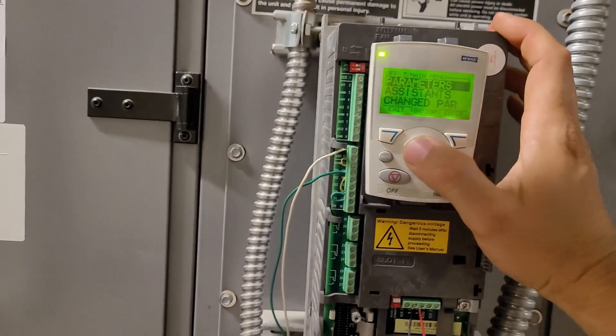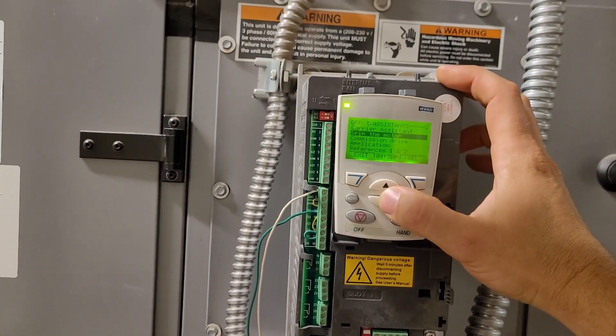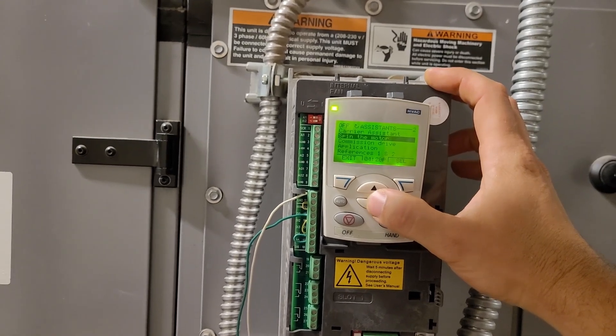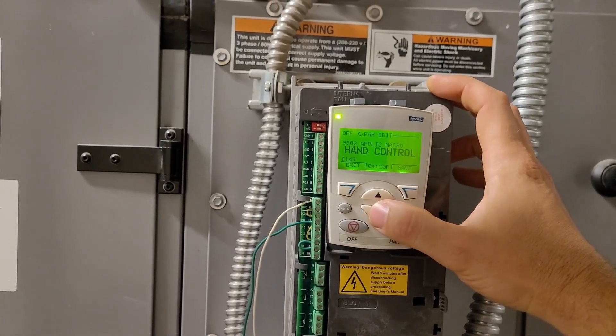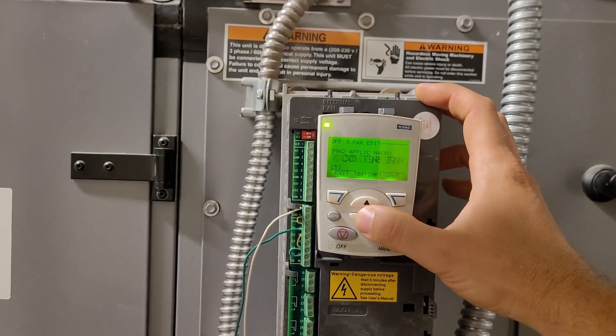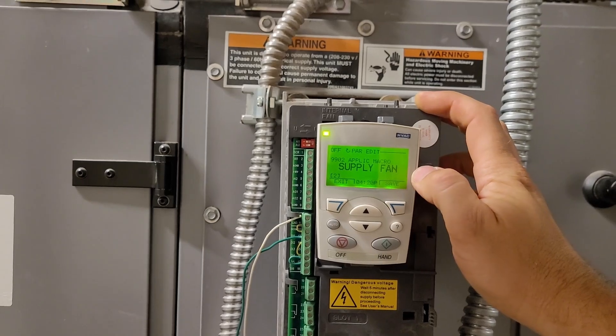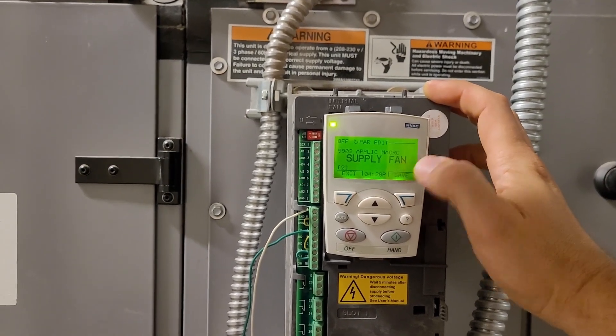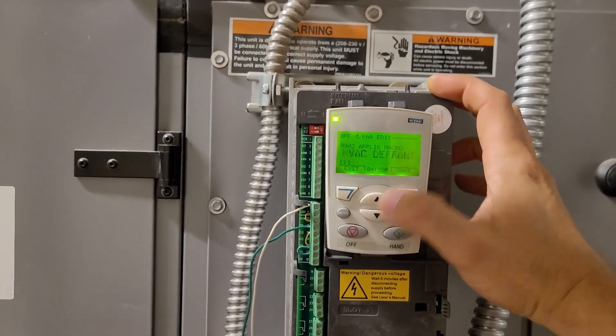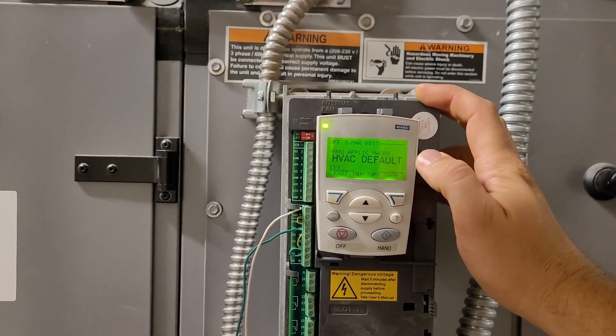What I ended up doing was going to Assistants, then to Application, and switching it to HVAC Default. Supply fan seemed like a pretty good option since that's what it's actually controlling, but that one was not useful. HVAC Default ended up being the one we wanted to use.